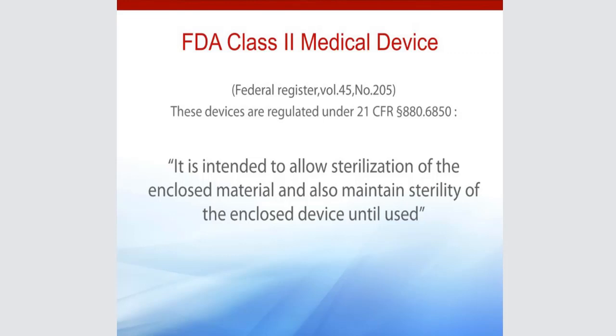So when we do things like sterilize unwrapped instruments, or we misuse the term immediate use steam sterilization, IUSS, we used to call that flash sterilization. That's meant for when you have maybe a specialty instrument, or you only have one of this particular type of instrument, and somehow it got dropped or contaminated, and you would need to run a quick unwrapped cycle. It would be delivered aseptically immediately from the sterilizer to the treatment room. Those instruments cannot be stored because they cannot maintain the sterility of the device.